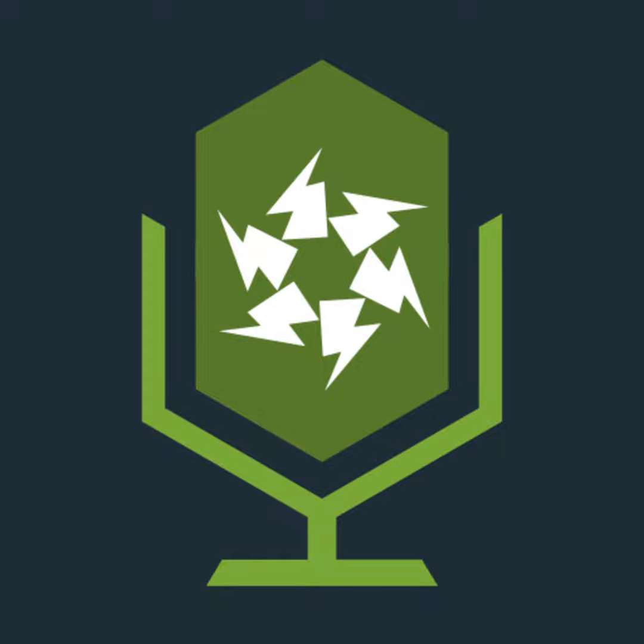I delta N is the rated operating current of the RCD, but we're talking about an earth imbalance, so we're saying milliamps: 100 milliamps, 300 milliamps, 500 milliamps, 30 milliamps, whatever that is. Okay, there's nothing that says it has to be 30 milliamps. It has to be appropriate, but it does say the voltage there must be no more than 50 volts. It must be less than or equal to 50 volts.